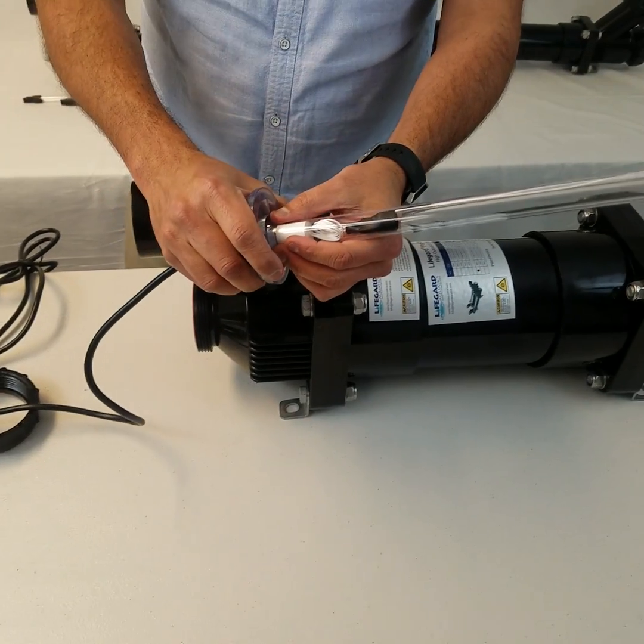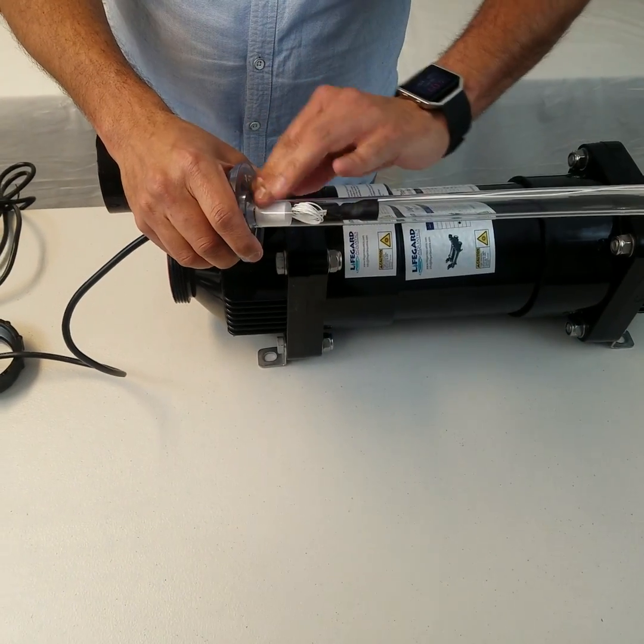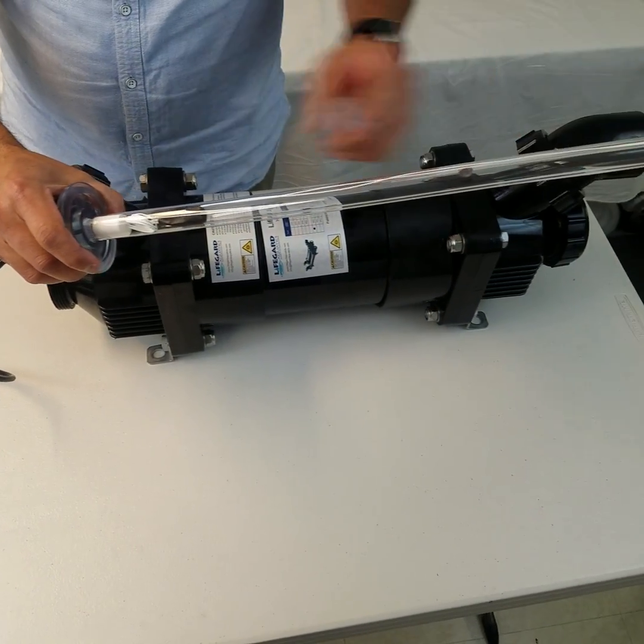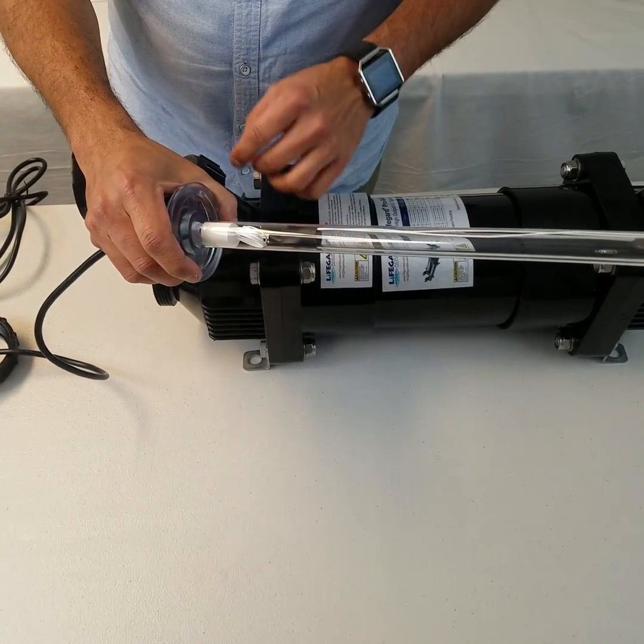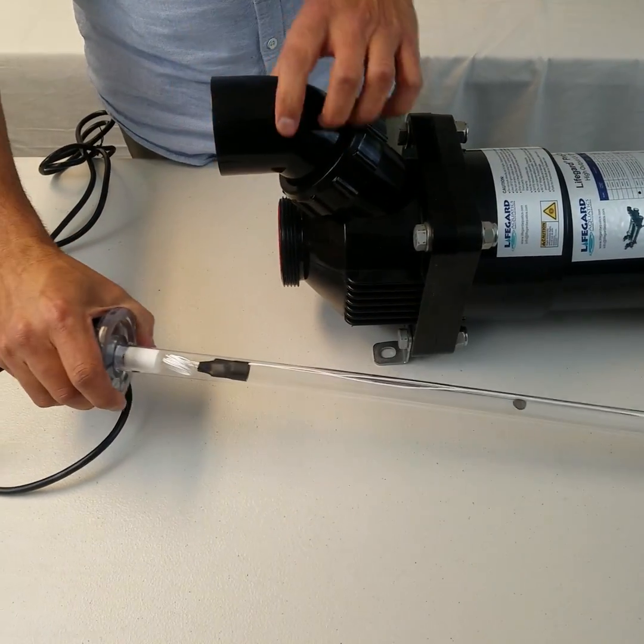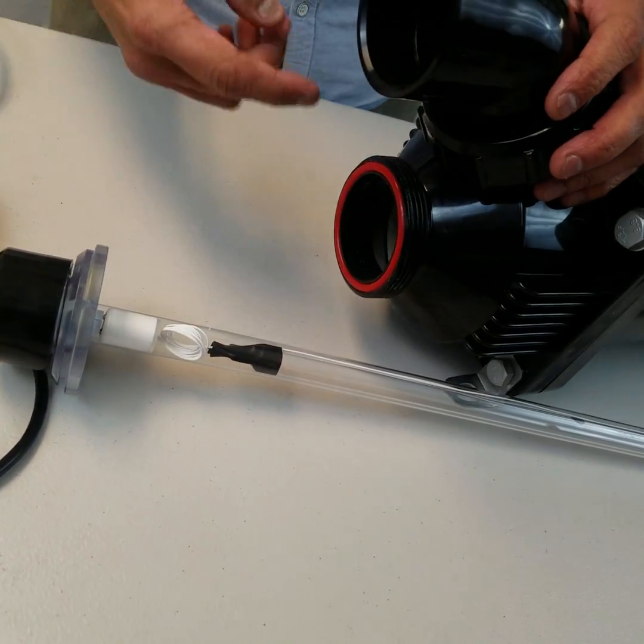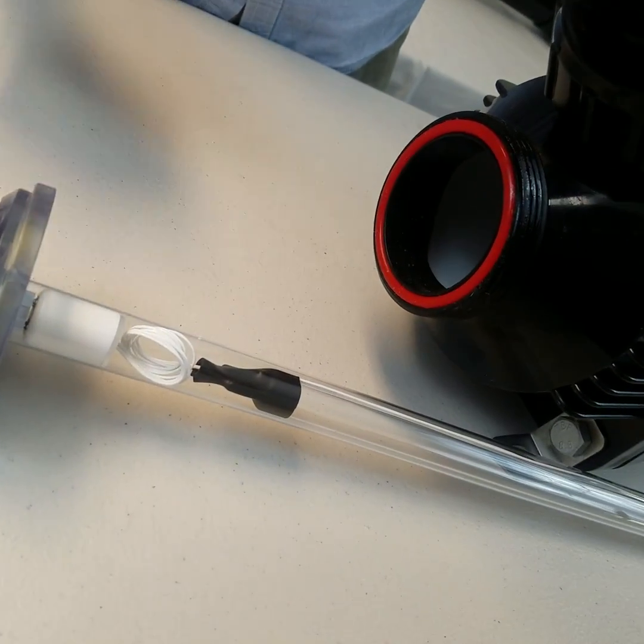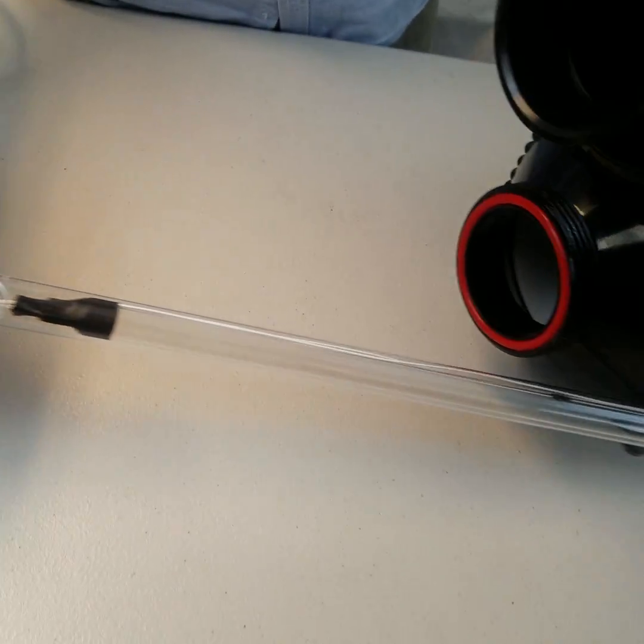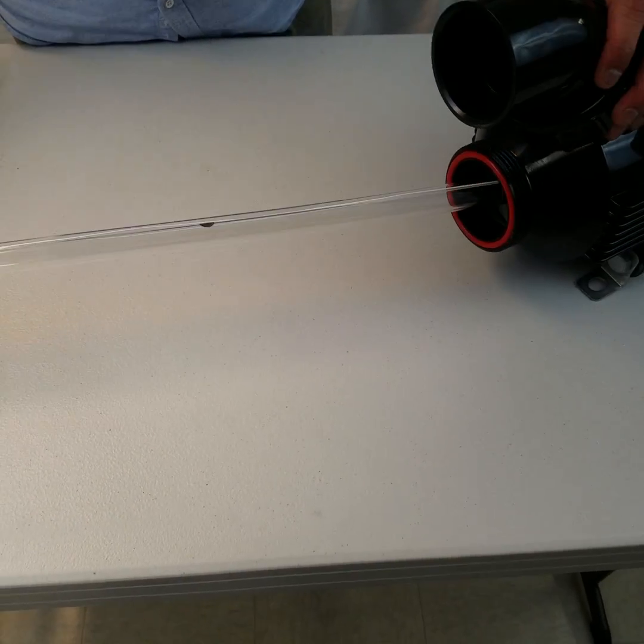On the o-rings there'll be silicone lubricant, so just make sure if silicone is on your fingers it's not on the quartz sleeve. Then you put it in straight. There is a receptacle for the quartz sleeve, which means that on this end is also a little receptacle which the quartz sleeve will sit in.